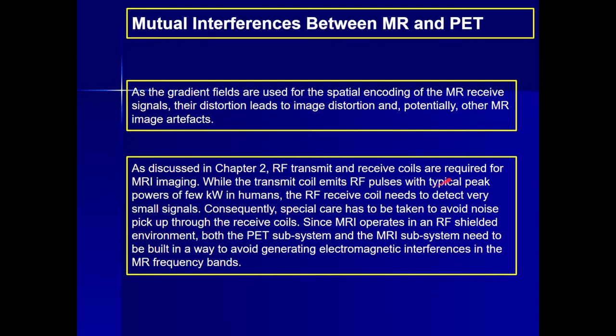RF transmitter and receiver coils are required for MR imaging. While the transmit coil emits RF pulses with a typical peak power of a few kilowatts in humans, the RF receive coil needs to detect very small signals. Consequently, special care has to be taken to avoid noise pickup through the receive coil, since MRI operates in an RF shielded environment. Both the PET subsystems and the MR subsystems need to be built in a way to avoid generating electromagnetic interference in the MR frequency band.